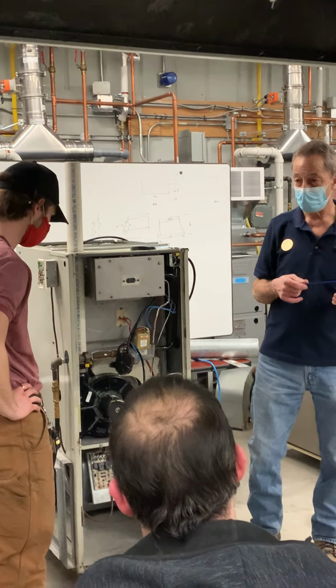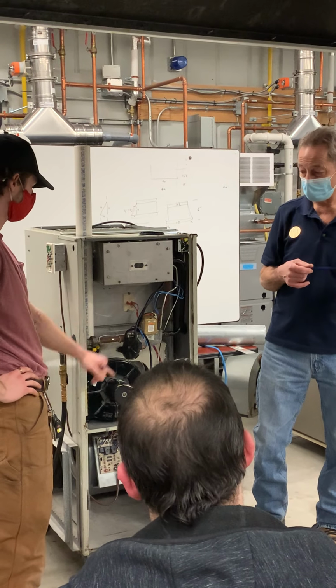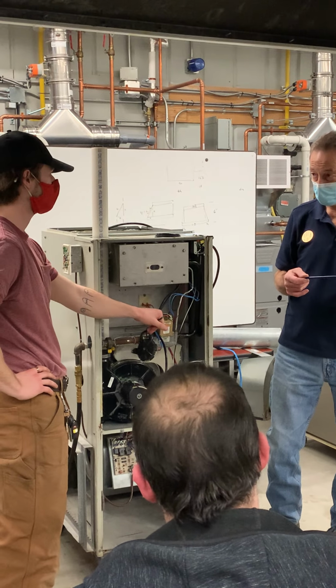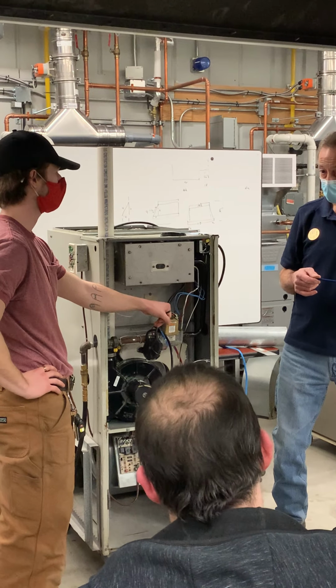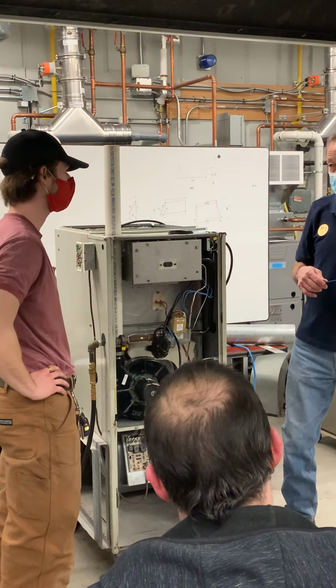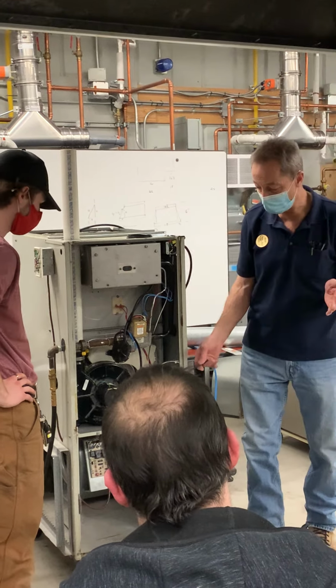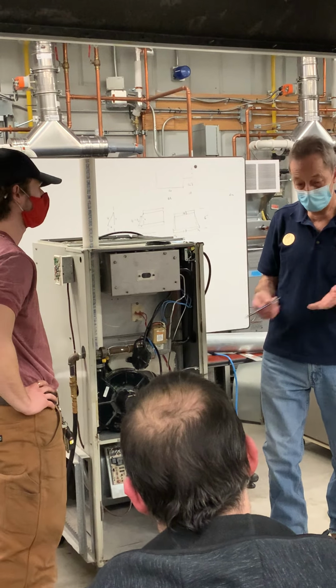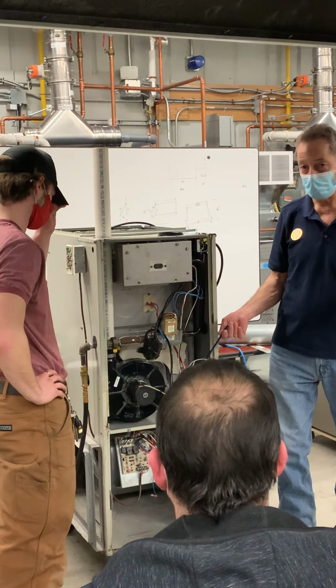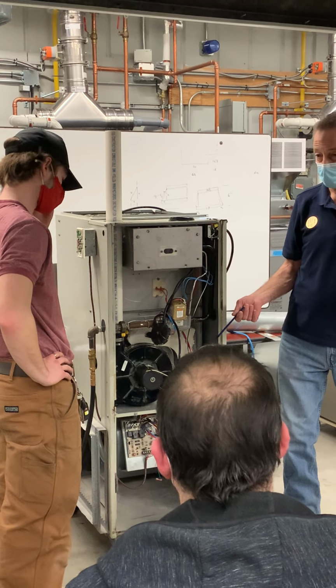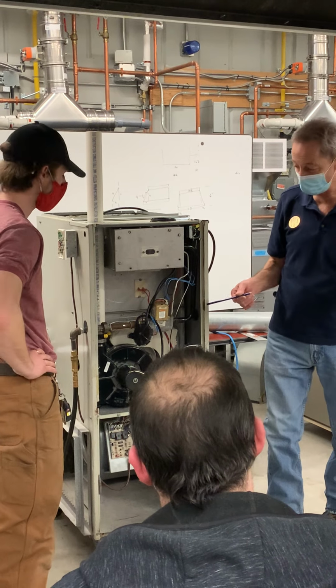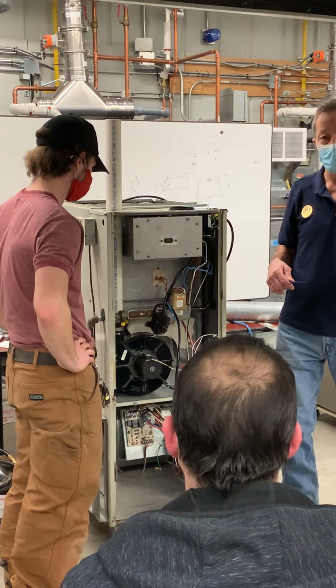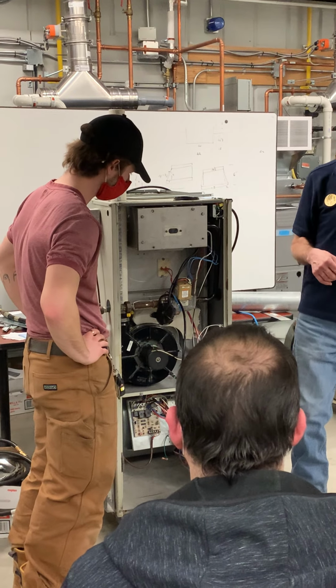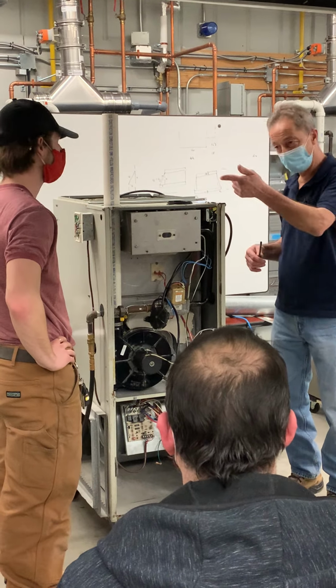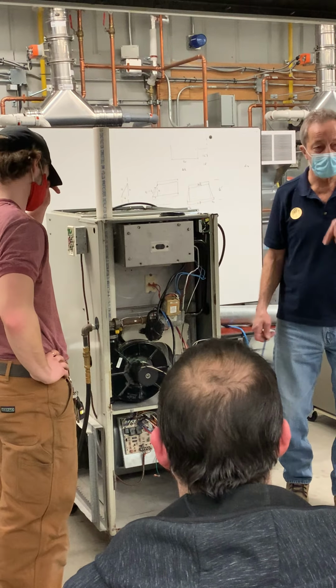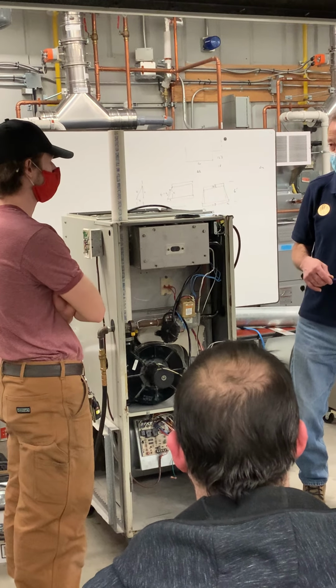If there was a loose wire or something with the valve, like when it's self-checking, you notice that? No, it won't pick up on that. So it could be that. Well, it could be a loose wire, or the wire's not on the right terminal, or it came off. Okay? Give me one more. It has to do with the orange wire. Is the valve defective? Could be a defective valve. Thank you. Defective valve. It didn't send a signal on the orange wire to tell the board to start timing.